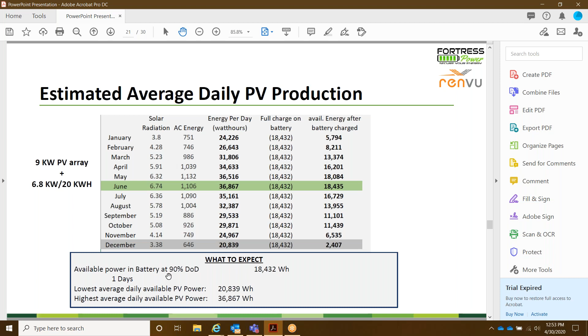So what we gathered is that the available power in the battery at 90% depth of discharge was 18,432 watt hours, meaning it will power the loads we saw earlier for one full day. That's essentially how our sizing tool works: based on the PV array and the electrical loads on the critical load panel, it determines how long a given battery size will power those loads.